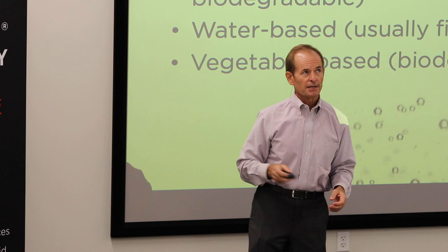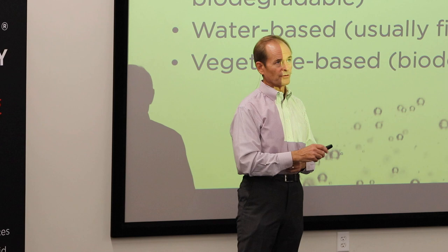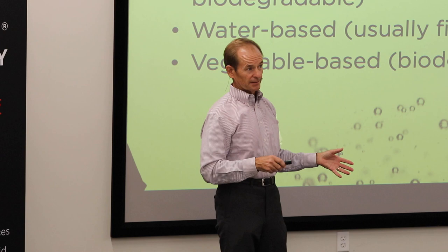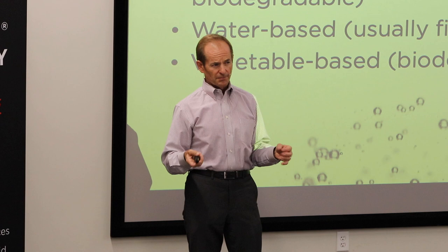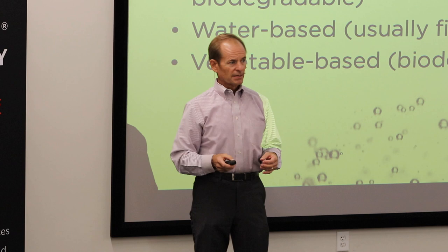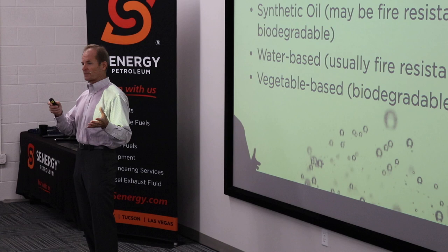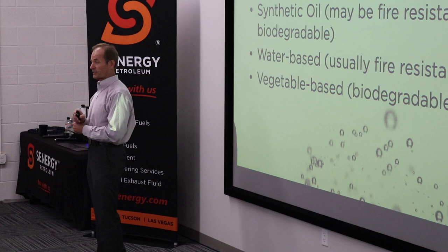The fourth kind of base stock you may see from time to time is vegetable-based, or vegetable oil-based. These are usually chosen because of their biodegradability. Vegetable-based stocks generally suffer from not having as good oxidation life, so they don't last as long in the equipment. They're also very expensive — some vegetable oils are more expensive than synthetics. There are places that actually require the use of vegetable-based hydraulic oils.